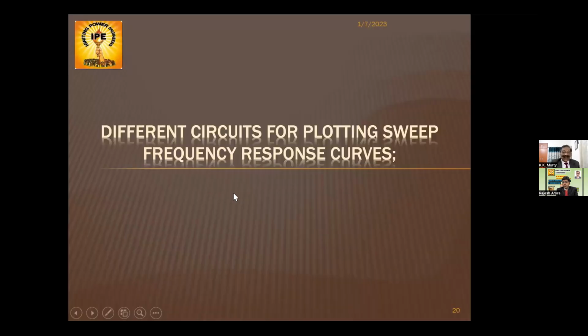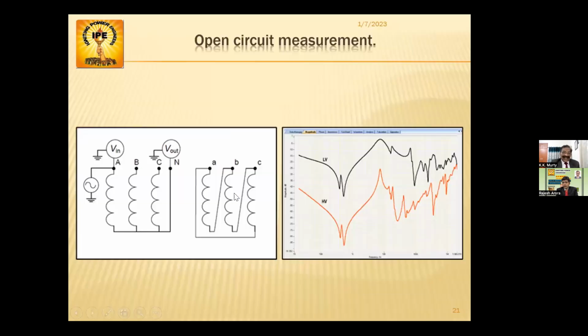So, different circuits for plotting sweep frequency response curves. There are 4 different practices. This is known as the open circuit scheme, in which the delta is open circuit. Say A, B, and C. In this, the ABC convention is used. You can see capital A, capital B, capital C is the HV side, which is star, and this is the delta, where A, B, and C are open. So the curve will come like this. You will find this curve like this.